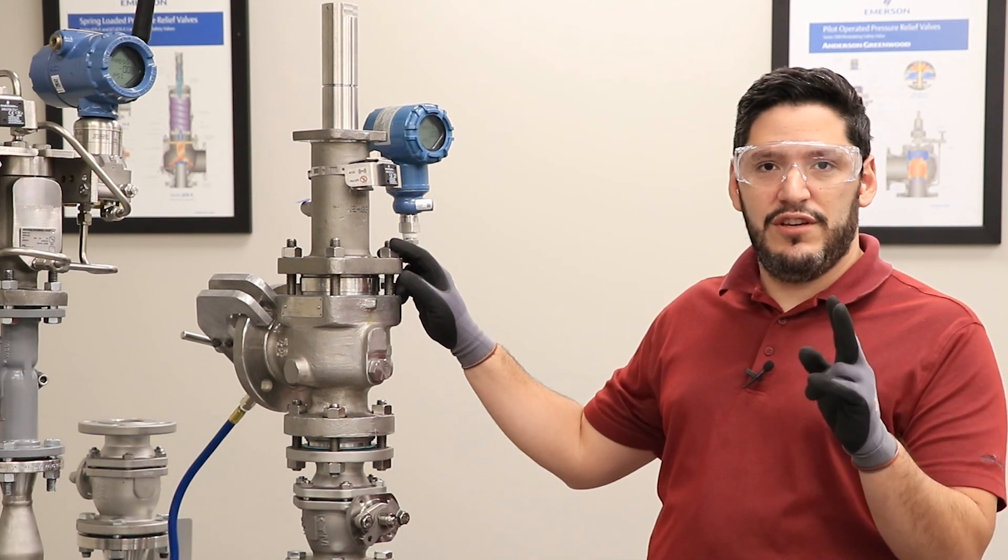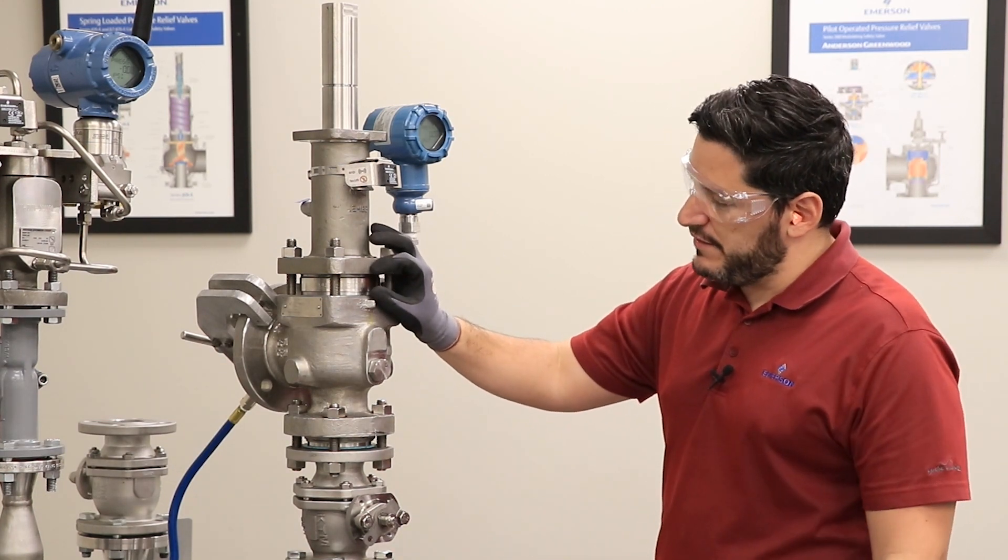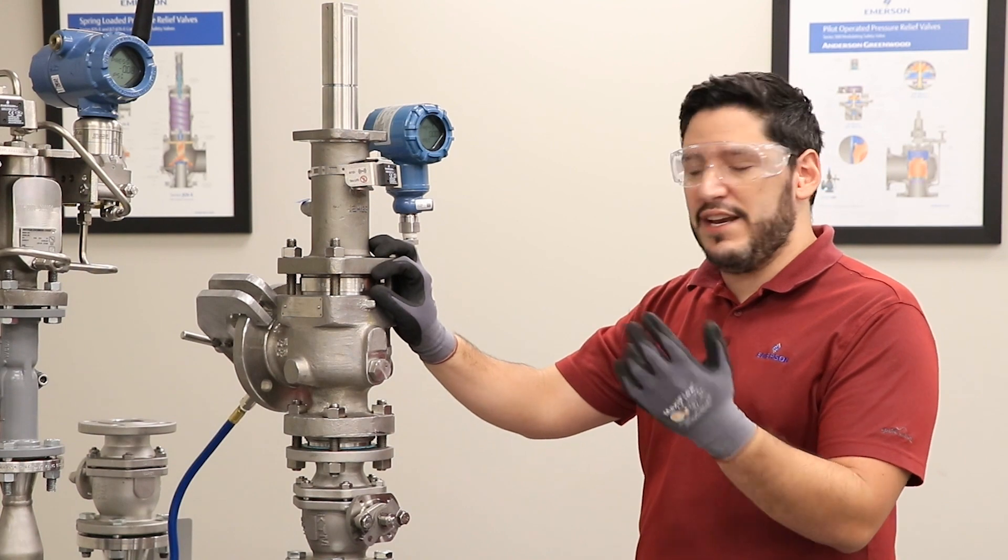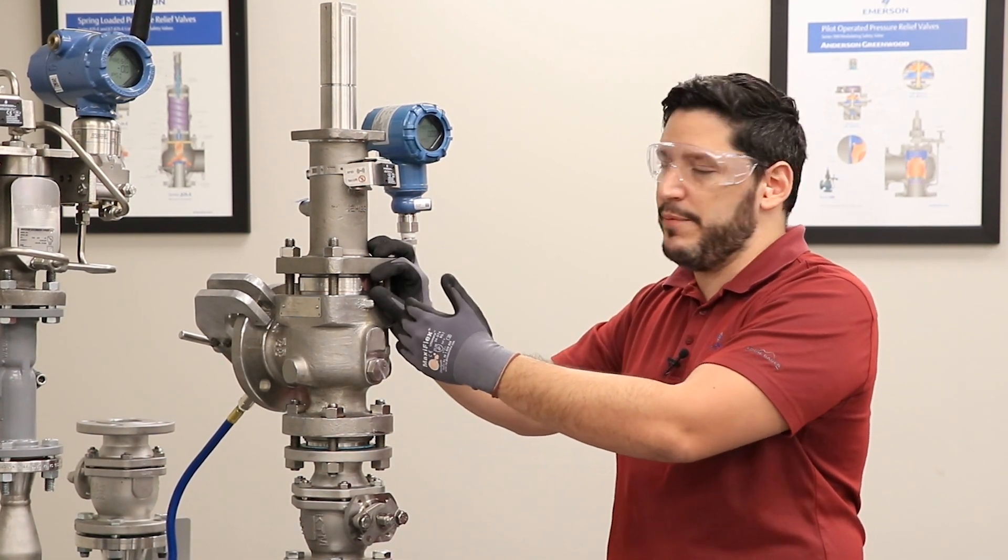Our solution entails two components. The first one is the backup piston. The backup piston ensures that even in the case of a bellows failure, the valve remains balanced against back pressure. It also reduces the fugitive emissions through the bonnet vent by up to 90%.